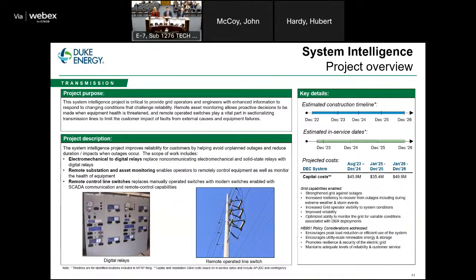We dispatch linemen. They have to go find the problem, sometimes going down very difficult to access right-of-ways through mountainous terrain, swamp areas. This leads to extended outage times. Once we do find the problem, we then need to go to a manual operated sectionalizing switch if there's one available, or just make the repair and restore the outage. So this combination of technology can take outages that have historically lasted several hours and turn them into several minutes. So it's a huge improvement for our customers.